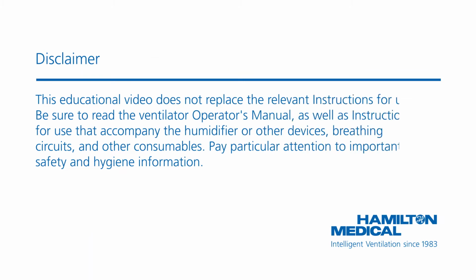This how-to video will show you how to set up the Hamilton S1 ventilator for ventilation on a specific patient. However, the procedure is exactly the same for the Hamilton-G5 ventilator. This educational video does not replace the relevant instructions for use. Be sure to read the device's operator's manual as well as instructions for use that accompany the humidifier or other devices, breathing circuits, and other consumables. Pay particular attention to important safety and hygiene information.